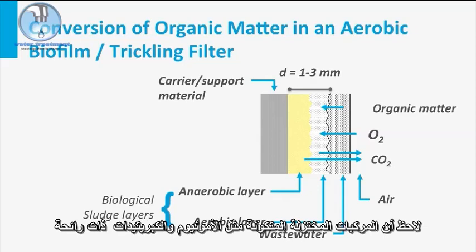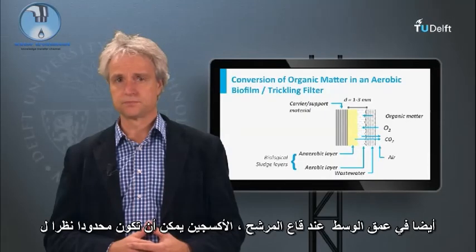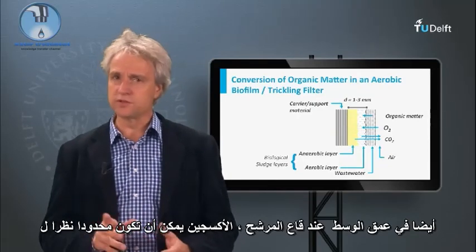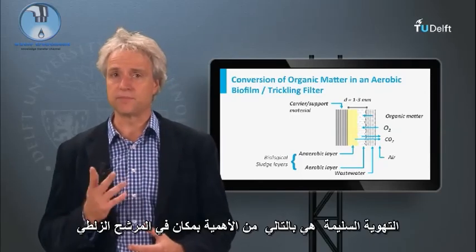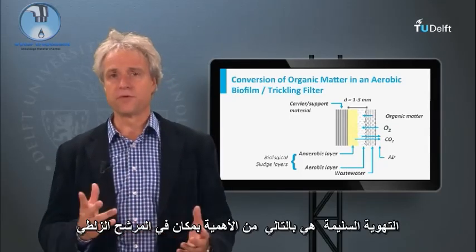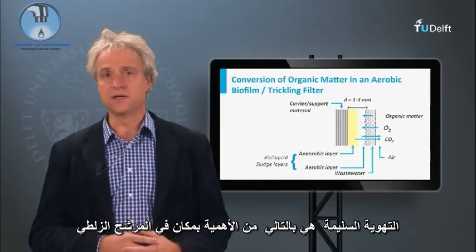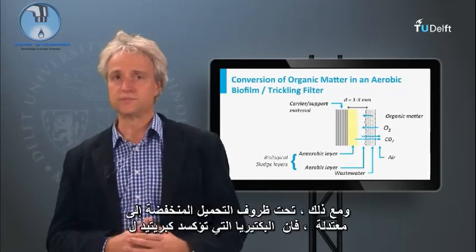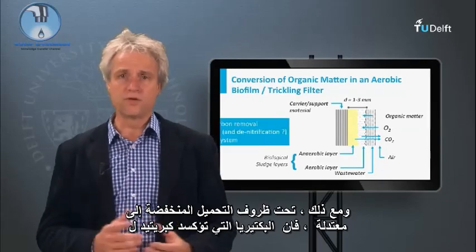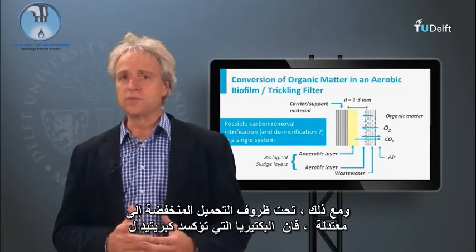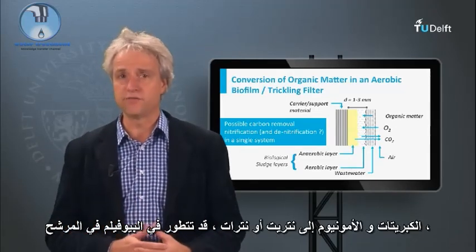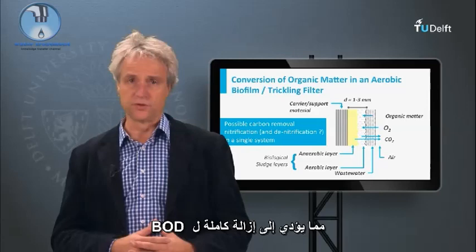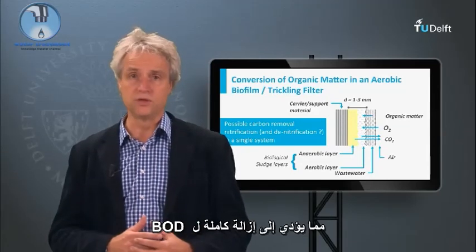Note that the formed reduced compounds such as ammonium and sulfide are odorous. Also deeper in the bed towards the filter floor, oxygen can be limited owing to the high biological activity at the top. Proper venting, or air supply, is therefore of utmost importance in the trickling filter. However, under low to moderate loading conditions, also the bacteria that oxidize sulfides to sulfate and ammonium to nitrite or nitrate may develop in the biofilms of the filter, leading to full BOD removal.